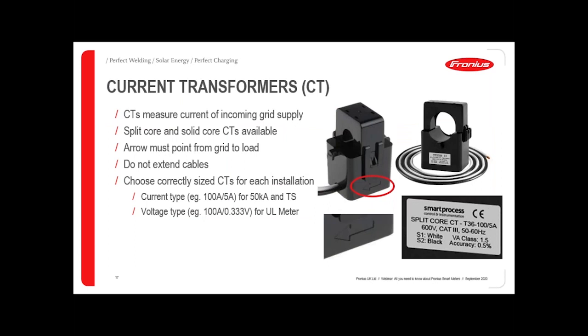We need to make sure that if we are using the current transformers, we're using the correct ones for the right meter and the right sizing ratio. The CTs measure the current from your incoming supply — they clamp around the incoming cables, one per phase. I'd always recommend using split core, which are hinged so you can clamp them around. If you have solid core, you have to disconnect the cables and feed them through the solid CT, so it's always better to go for split core. It's very important to make sure each CT has an arrow printed on it, and that that arrow is in the direction from the grid to the load within the building.